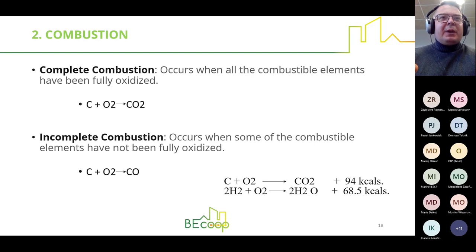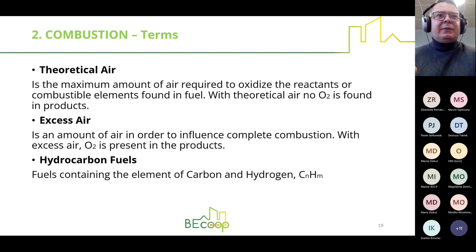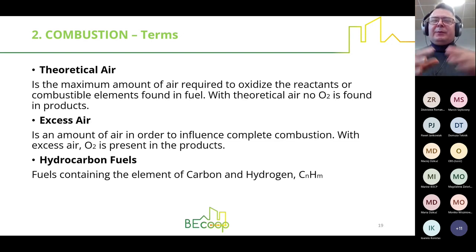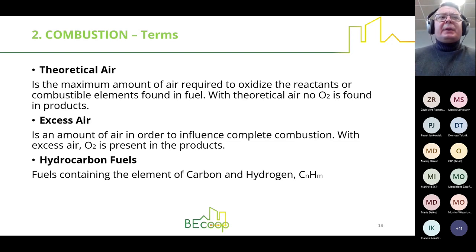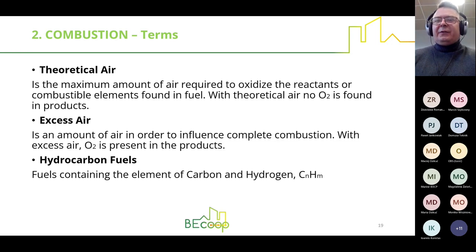Complete and incomplete combustion can occur. From a practical standpoint, what is important is the theoretical air — the maximum amount of air required to oxidize the combustion reactants. It is crucial to mix the solid biomass with air as well as possible, meaning the biomass should be milled and ground to a specific size and mixed thoroughly with air. That is the key to efficient combustion.